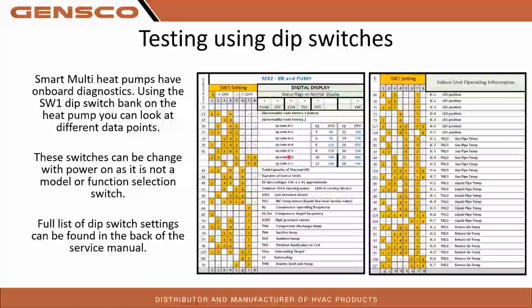As far as those status flags I was telling you guys about that you will normally see on your display, this is what they mean. If you have a 1 in segment 1, LED 1 there, it means your compressor is on. Segment 2, your 52C relay is closed in the system. Your 52C relay can be in your power board or control board, depending on the unit. It's a relay that closes once the system is getting ready to start.